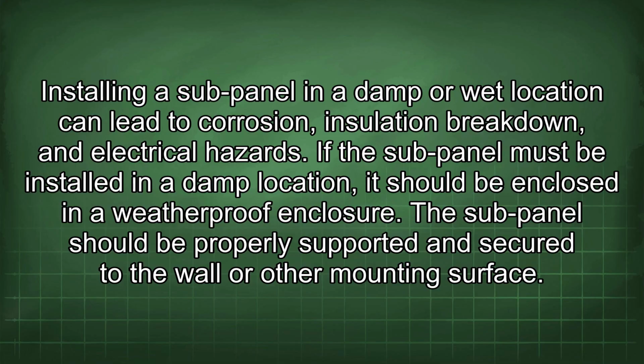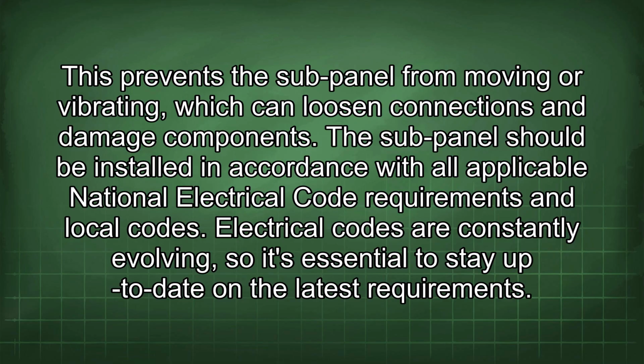If the sub-panel must be installed in a damp location, it should be enclosed in a weatherproof enclosure. The sub-panel should be properly supported and secured to the wall or other mounting surface. This prevents the sub-panel from moving or vibrating, which can loosen connections and damage components.